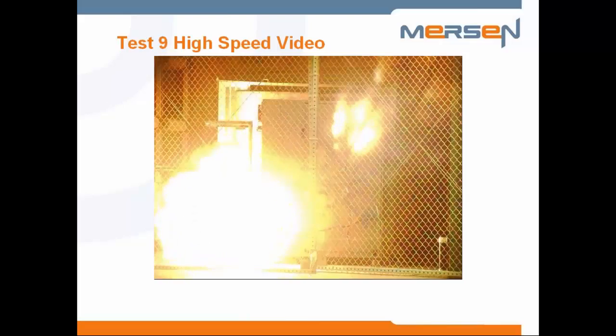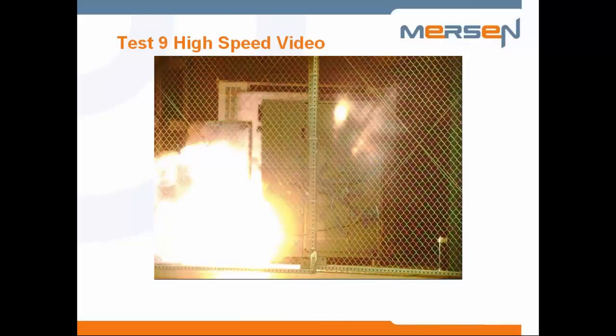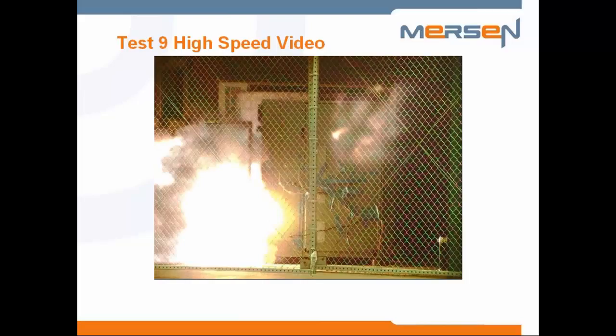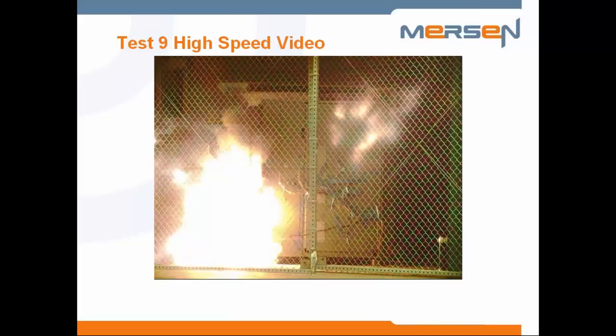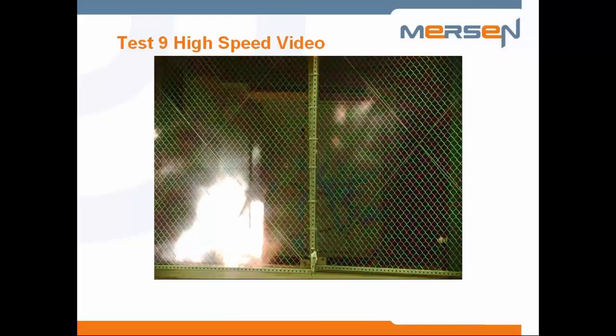With the high-speed camera, you can see the outward movement of the plasma to the left. But what's also interesting in this is that even though the door was open and the plasma is being ejected outward, there was plasma and hot gases visible in the rear of the enclosure, which shows that the plasma was not just electromagnetically ejected, but it thermally expanded throughout the equipment.